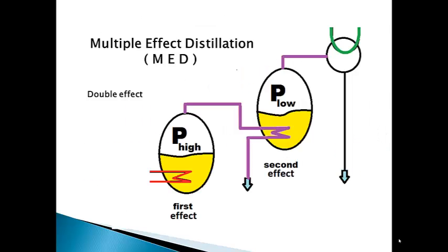Distillation may be carried out using multiple chambers with progressively lower temperatures and pressures. This is known as multiple effect distillation, or MED. Here is a two-effect or double effect unit. The high pressure vessel is heated by plant steam, while the low pressure vessel is heated by the vapors generated in that first vessel. The advantage of this arrangement is that the heat from the plant steam gets used twice. The energy cost per kilogram of distillate is cut roughly in half.